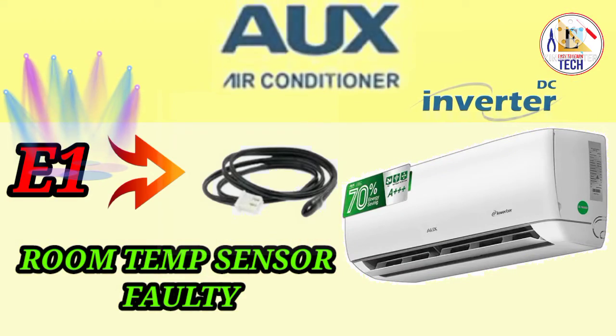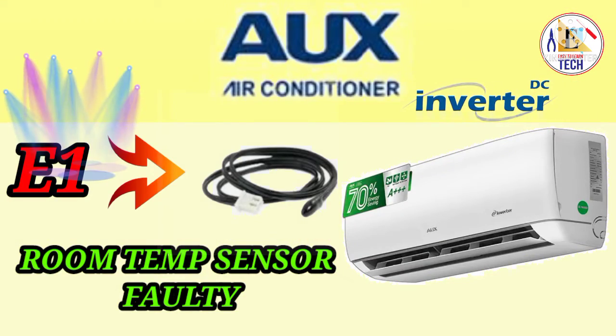Let's see the first error code. When you see E1 on the indoor display of your AUX inverter air conditioning, it means the room temperature sensor is faulty. As you can see in the picture, this is the room temperature sensor installed in our indoor unit. First of all, you have to check the placement, then check the connection in the PCB to see if it is connected properly or not.